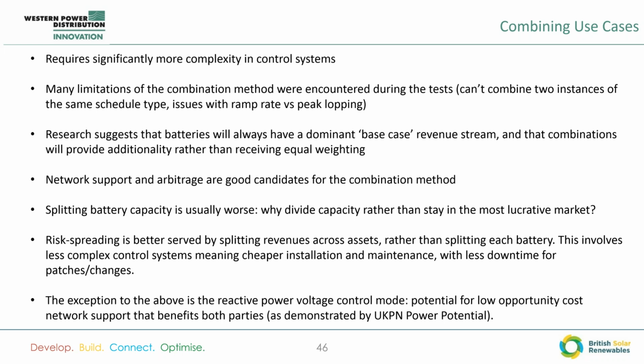And the only exception is the reactive power control mode with that non-linear trade-off. UKPN's Power Potential is demonstrating multiple assets working with reactive power, and that's quite good. Each one sacrifices a little active power, or sometimes they don't sacrifice any. If they're generating at peak, they don't offer the reactive services, but at all the other times when they're not generating at peak, they're offering reactive power flow to the grid.